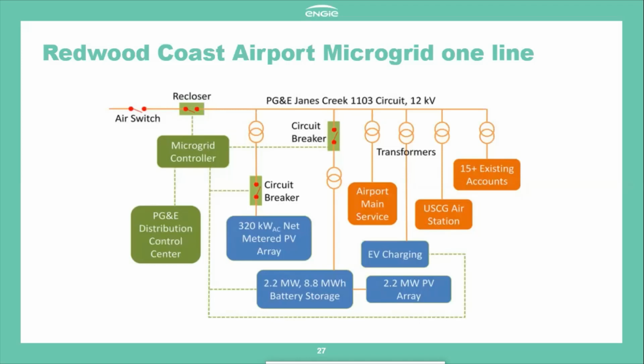Exactly. So what you do is you program into the microgrid controller grid outage situations, and the reason why in the winter is there isn't enough solar production, and so you're having to rely on the grid to charge the batteries. The example I gave in the morning is where the battery storage usually would be at its lowest level because it's expecting the PV to turn on and repower it. And so in those scenarios, if you don't oversize the battery, you're hoping that the PV would have recharged those batteries. So as a default, you say, okay, if this worst case scenario happens, what can we curtail? And it may only be a month out of the year.